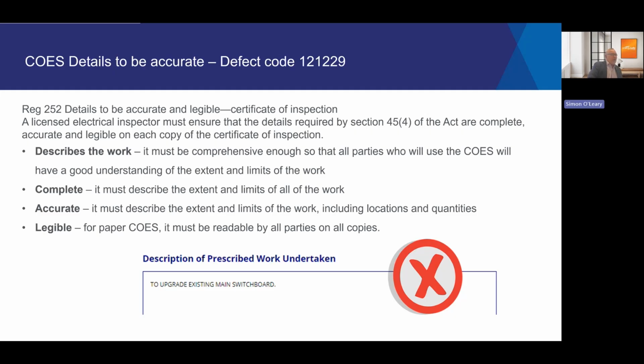This is for a number of reasons. These certificates are used by different individuals throughout the certificate's life. It could be the owner, the electrical inspector, building surveyor, and also Energy Safe Victoria and our auditors. So a description that is as short as to upgrade an existing main switchboard doesn't give a clear description of what work was actually carried out. Did that include consumers' mains? Did that include main earthing system?